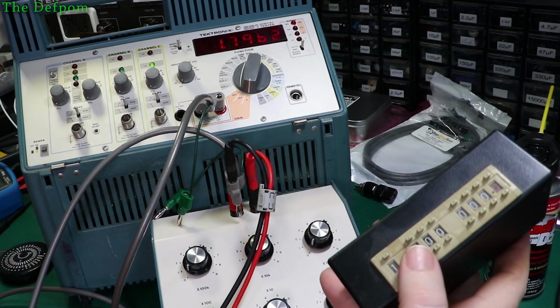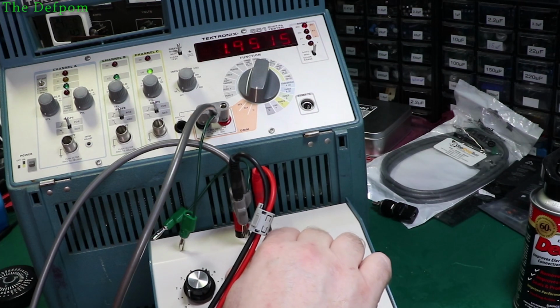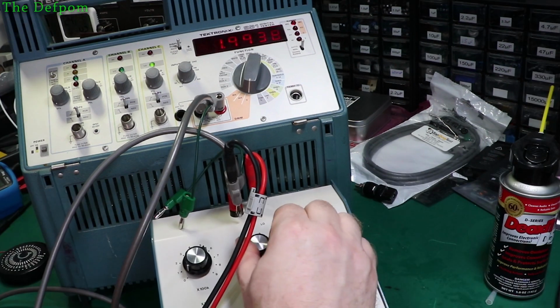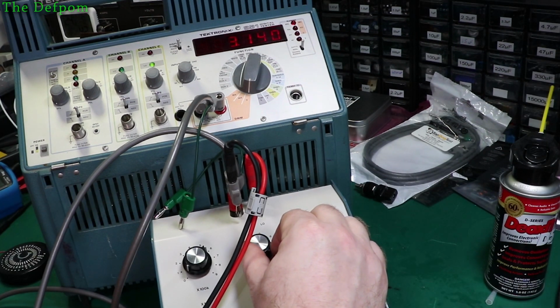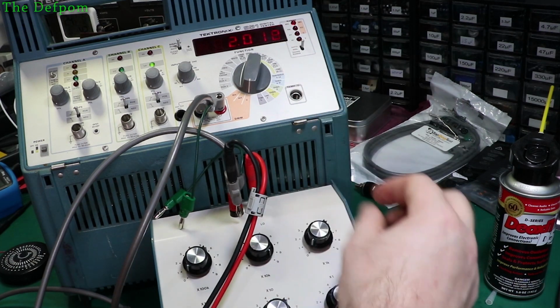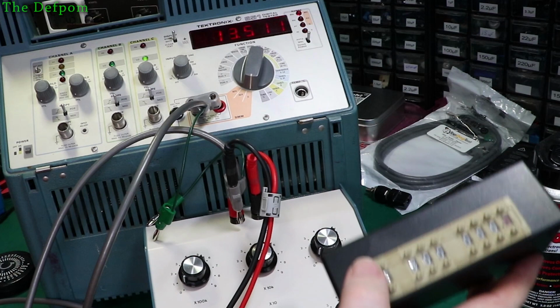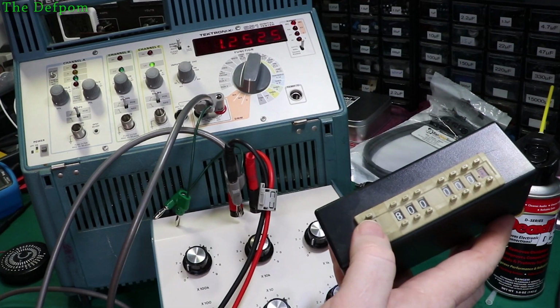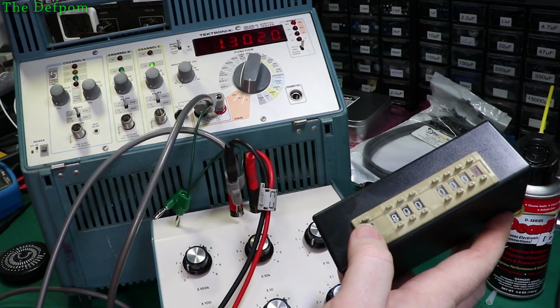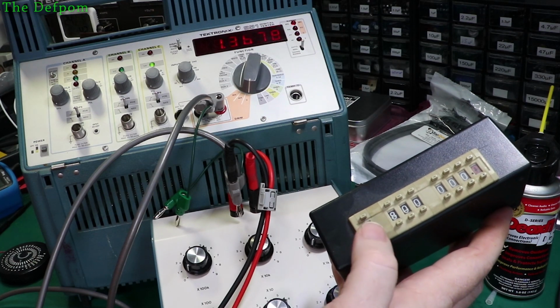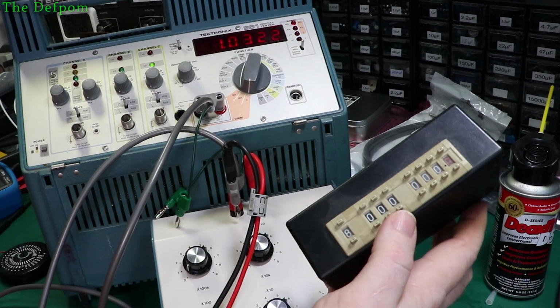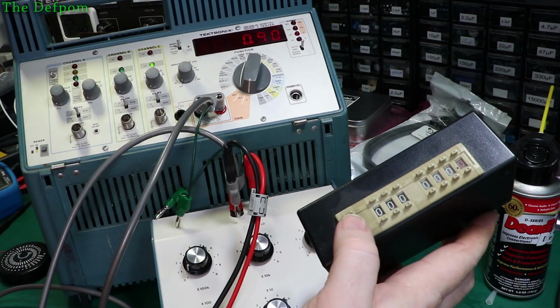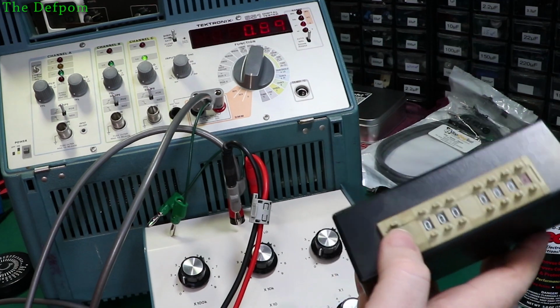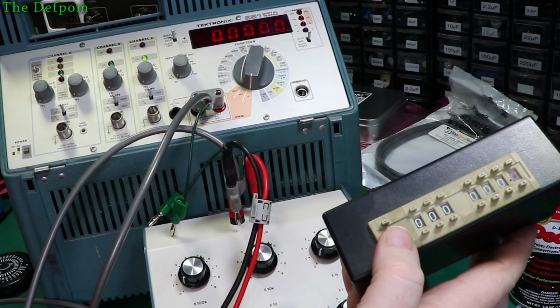This isn't a great box. Trying to get to the threshold where it jumps over to 2. There you go, changed over there. And that's reading okay. Let's put these back down again. 0 of those. 2.8. Not reading correctly. So I think this is using the relay I swapped out, I think it's using that one now. Because that isn't reading any more than 1 megohm. Interestingly, it states a 50 megohm range.